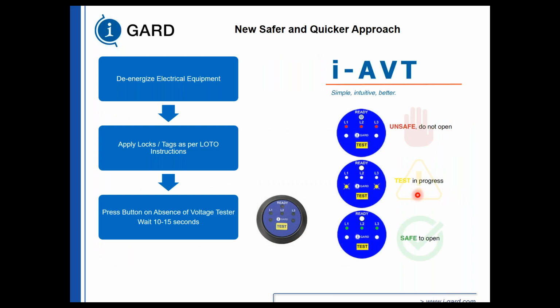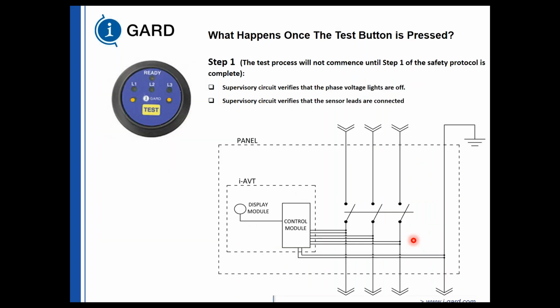So the new method now of rendering gear safe, or verifying the absence of voltage and having an electrical safe workplace, is to de-energize the equipment using the normal method that you had before. You still need that up-to-date single line. Apply the lockout tagout, press the test button on the display unit, and then if you get 3 green LEDs, it's safe to open that door. We've gone from a 20-minute procedure to a 20-second procedure. So this is what happens. Step 1.